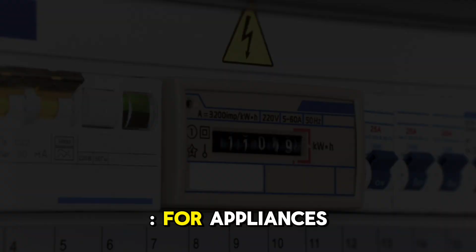The 220 to 240V system, for example Europe. Advantages: more efficient power delivery. Less energy is lost as heat, and smaller currents allow for thinner, cheaper wires. Better for high-power appliances. Large appliances like air conditioners and ovens can run more efficiently with lower current and less strain on the electrical system. Disadvantages: higher risk of shock. Higher voltages carry a greater risk of electrical shock, though modern safety standards and devices like circuit breakers and residual current devices mitigate this risk.